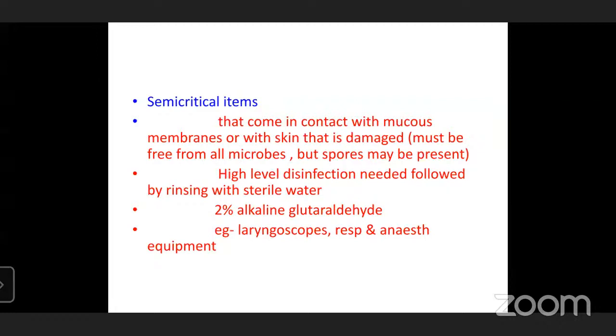The next level is semi-critical items. These are items that come in contact with the mucous membrane or with damaged skin—things like a laryngoscope, an endotracheal tube, or respiratory and anesthetic equipment. These come into contact with respiratory or mucous membranes, or skin that is partly abraded or damaged, so we need high level disinfection for them. A 2% alkaline glutaraldehyde is what is required to disinfect these items. So now we know what high level disinfection is and what we use for it, and why a particular item needs it—because it's going to touch the mucous membrane.